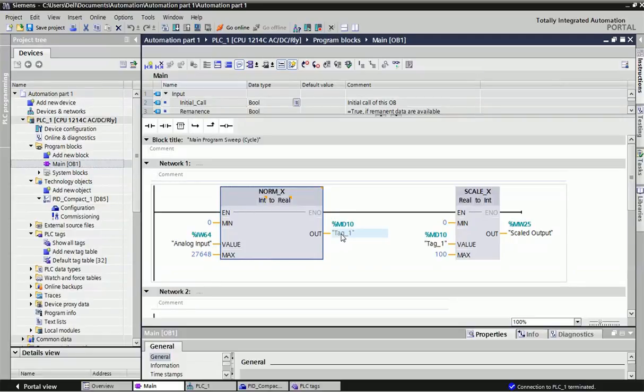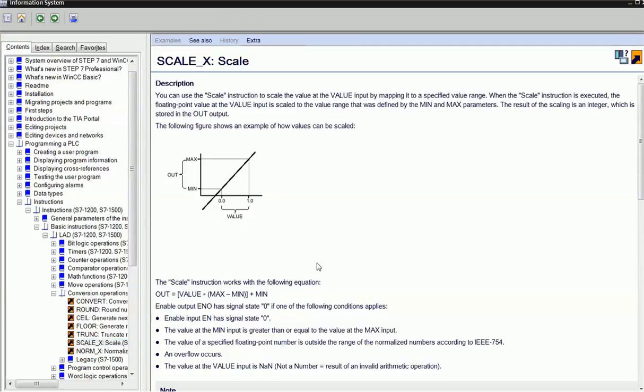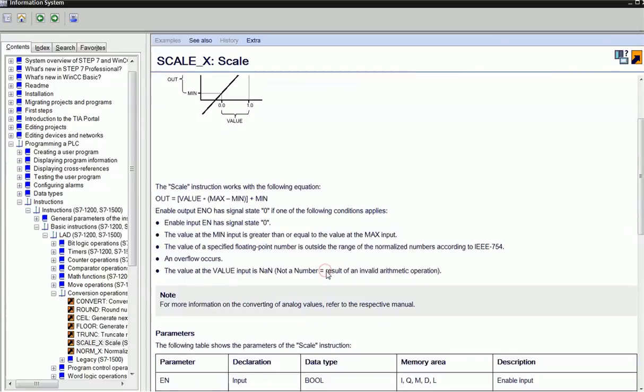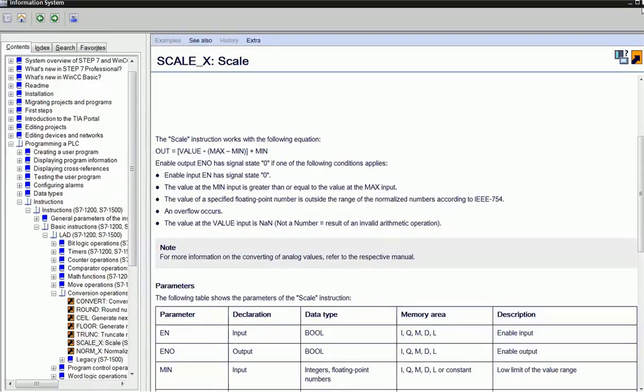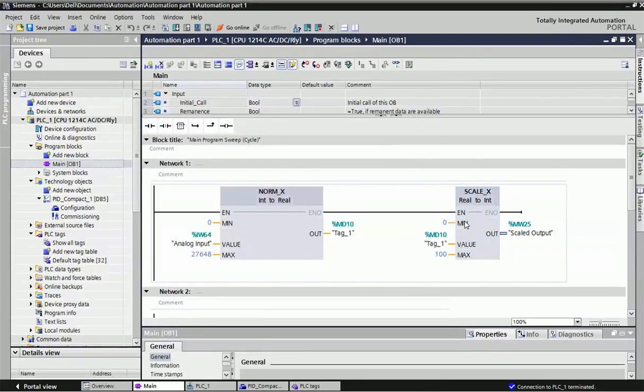This data we will put again in the SCALE_X block. SCALE_X block is the final equation for linear scaling. This equation is ultimately y equals mx plus c. Here I have converted this scaling into 0 to 100 maximum range. That range you can change as per your application or demand. I assigned MD10, and finally the scaled output we will get from MW25. This scaling value you can use in any applications - you can move this value to SCADA, HMI, or further applications.